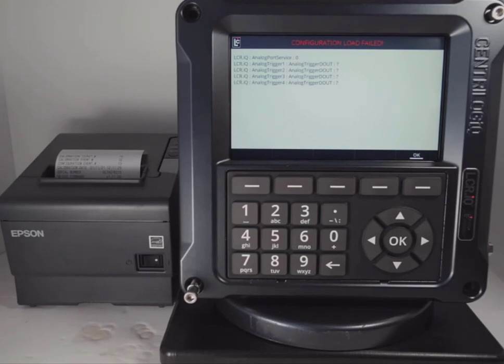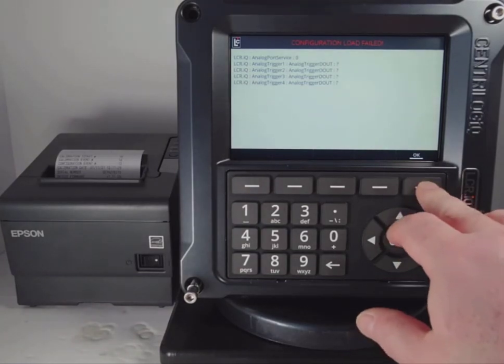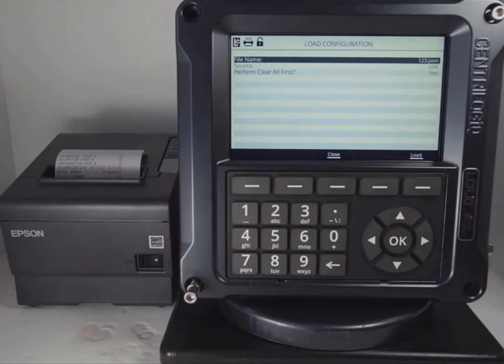Because those weren't in version 108 and are now in version 111, this screen is just telling us there are fields in those analog triggers that do not exist in the software when they were loaded onto this register. Since I wasn't using that feature in version 108, it's fine to just hit OK and clear that message.